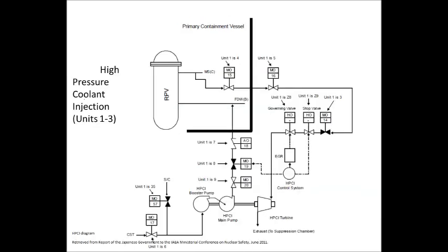The purpose of the high-pressure coolant injection system is to supply makeup water to the reactor pressure vessel when it is isolated from the turbine condenser to maintain reactor pressure vessel level. It is 7 times the flow rate of the makeup portion of the RCIC system. This system operates similarly to the RCIC system, but has a higher makeup water capacity.